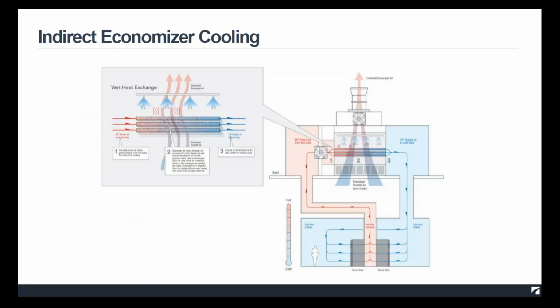All right, indirect evaporative economizer cooling. So I mentioned in Central Washington, we use indirect economizer cooling. And so essentially how this works is we are adding moisture to the outside dry air that cools the temperature of that outside air. And we use a heat exchanger that transfers that heat between the data center air and the outside scavenger air. Again, we use that in our Central Washington facility. This diagram also shows, similar to some diagrams Steve showed, that ideal situation where you're flooding the room with cool ambient air, but not cold, just like 70-degree air. And in the hot aisle, it is very hot. We have measured temperatures of 100 degrees in our hot aisle, and that's okay. That's what they should be. Next slide, please.